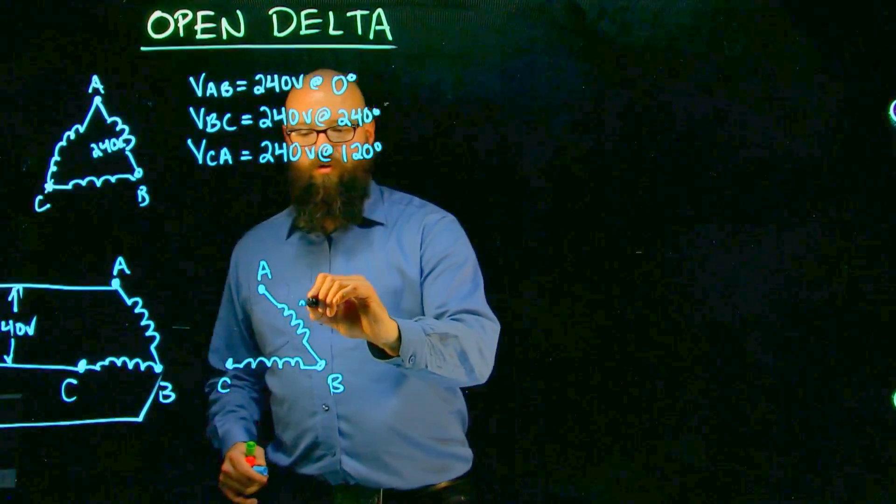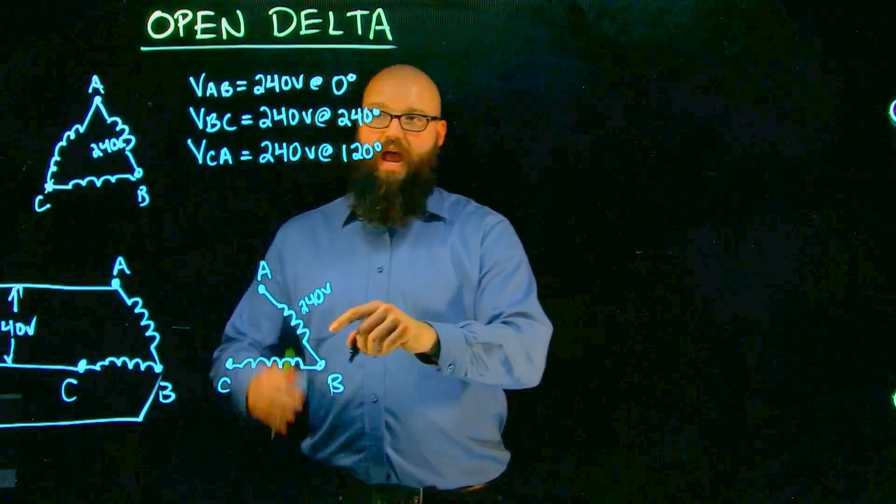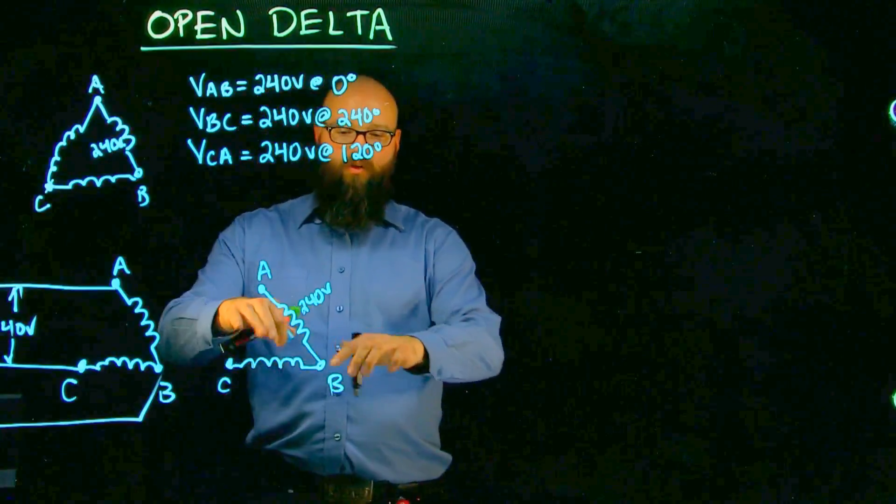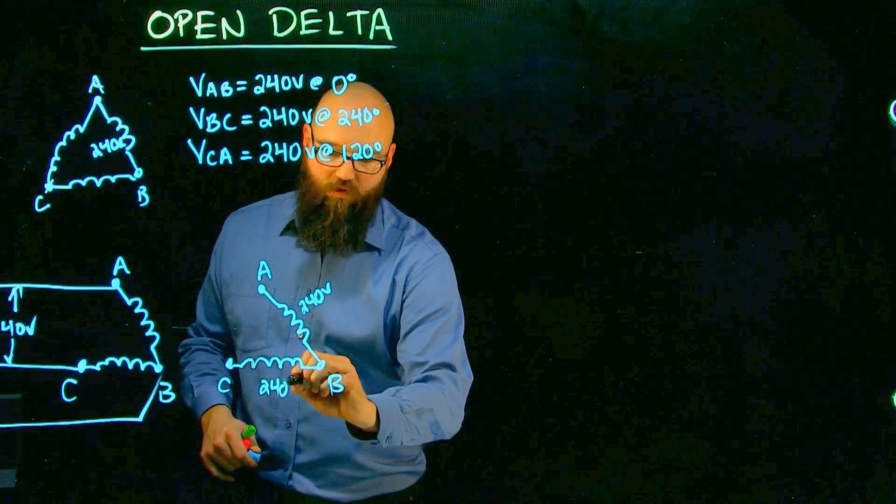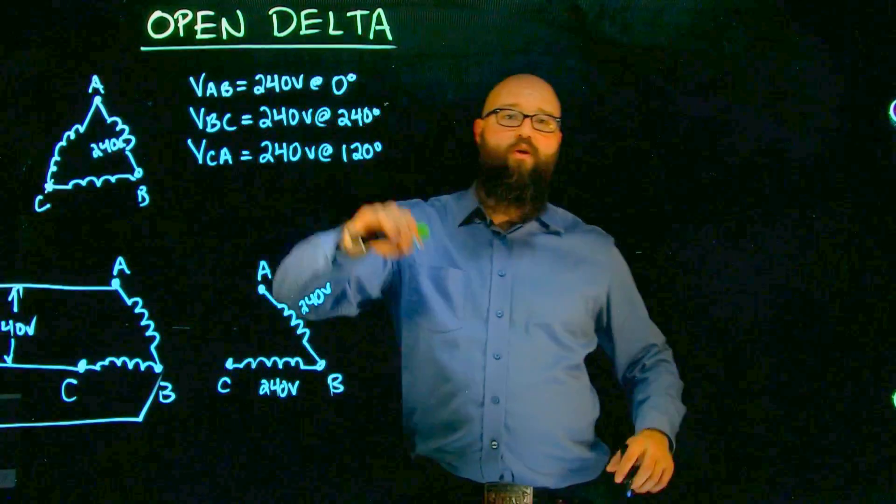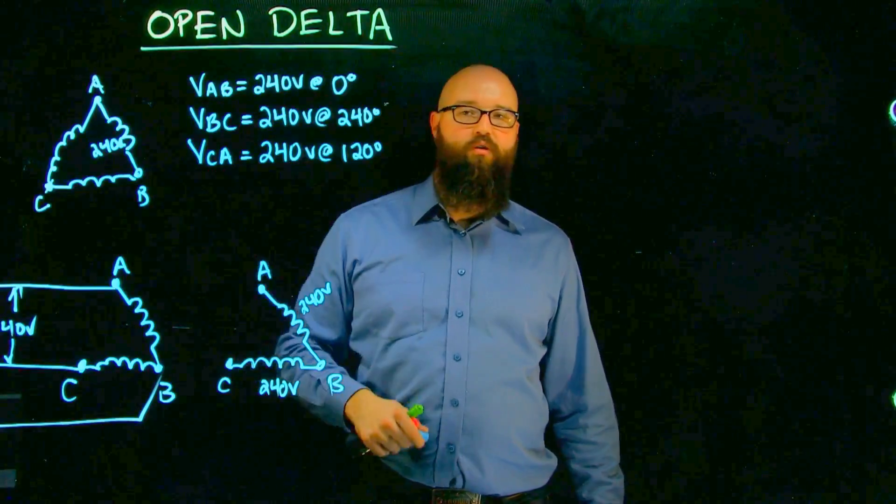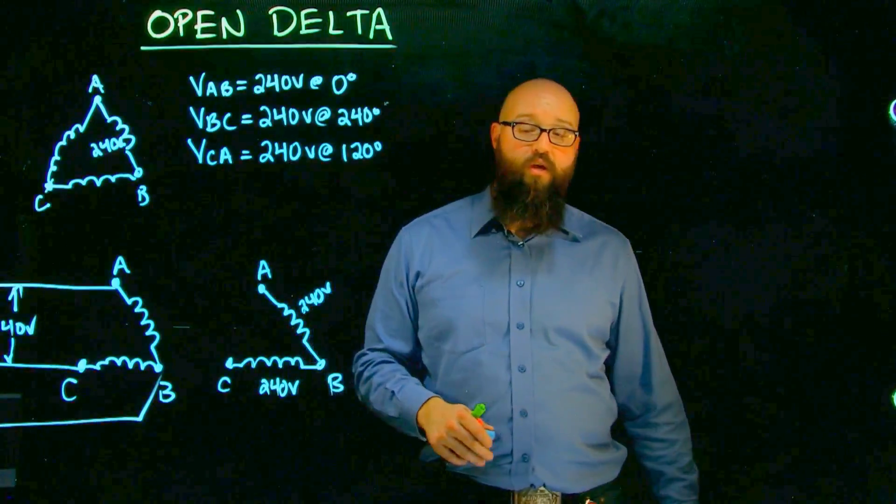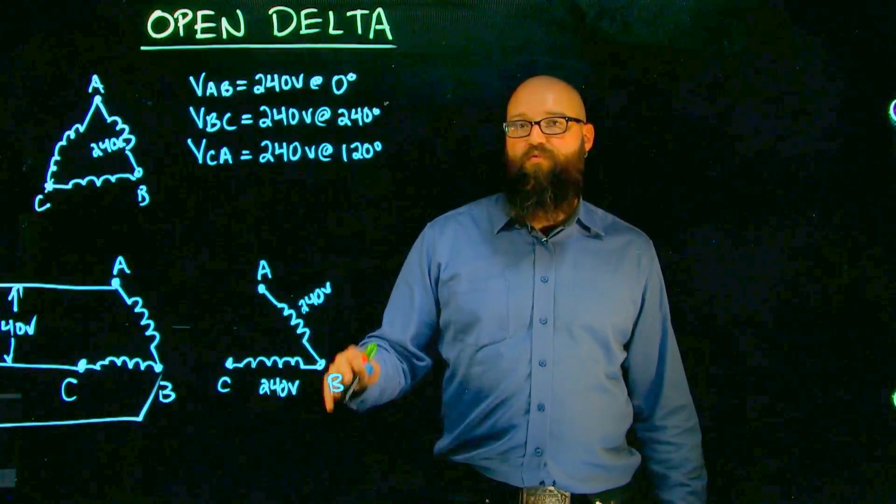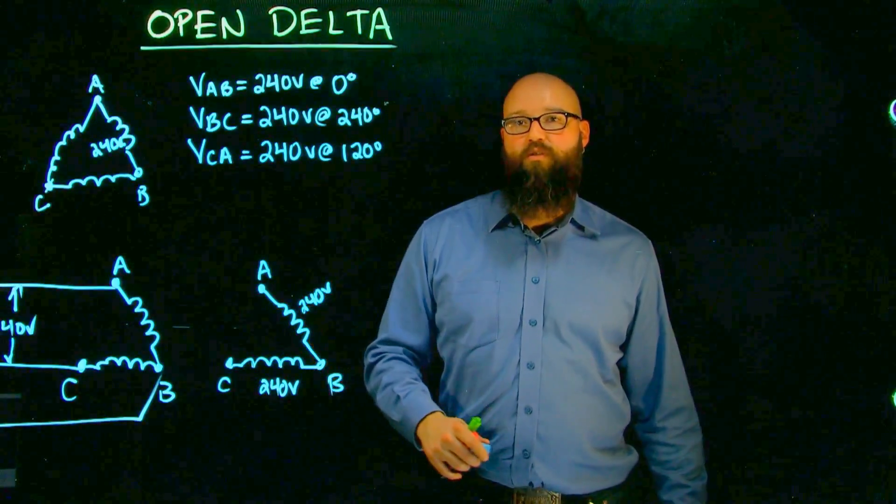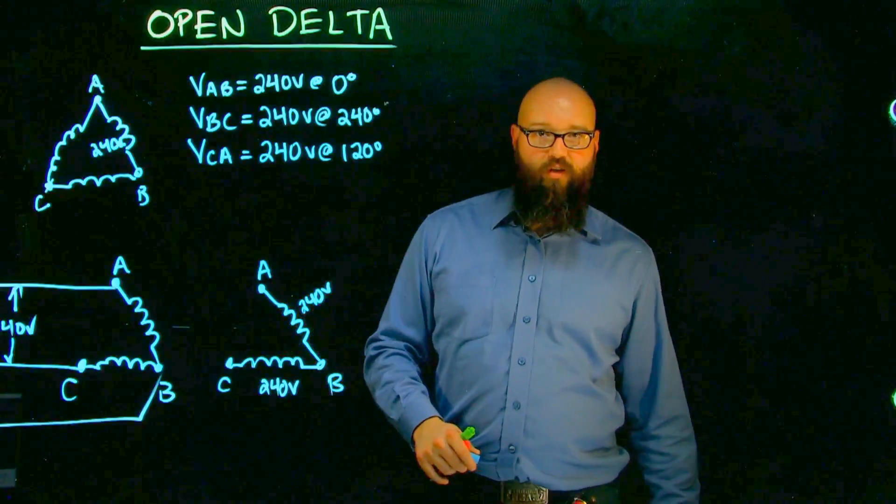We still have our 240 volts at 0 degrees. We still have our 240 volts at 240 degrees. What was lost, though, was this V C to A, which was 240 volts at 120 degrees. But what we're going to do right now is prove that that is still there and available to us as a voltage from our transformer.